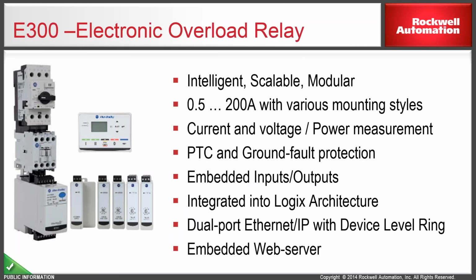So this is basically an E300 electronic overload relay, and if I compare it with the normal thermal and magnetic overload relays, first of all it gives you accurate information because electronic coils are being used. It is not based on the thermal or temperature sensing of the motor, right? So it will give you accurate information and trip at the accurate time. It is intelligent. It has a dual port Ethernet port built into it. It is scalable in nature, so you can expand if you have certain requirements of IOs. It is modular, so we will get into further slides on it.